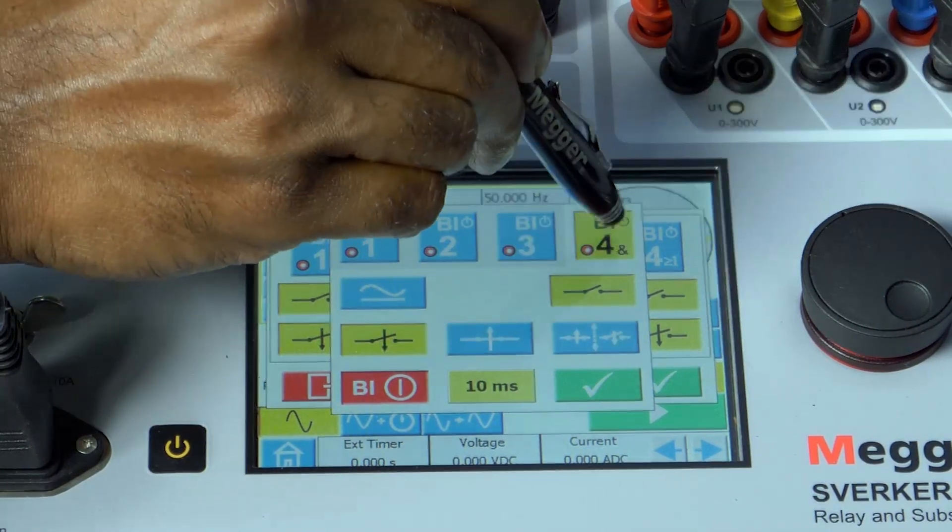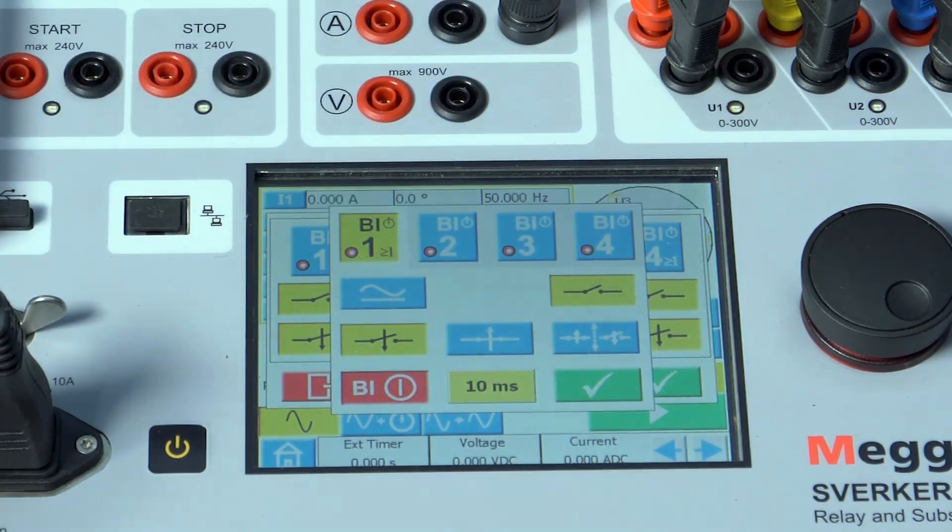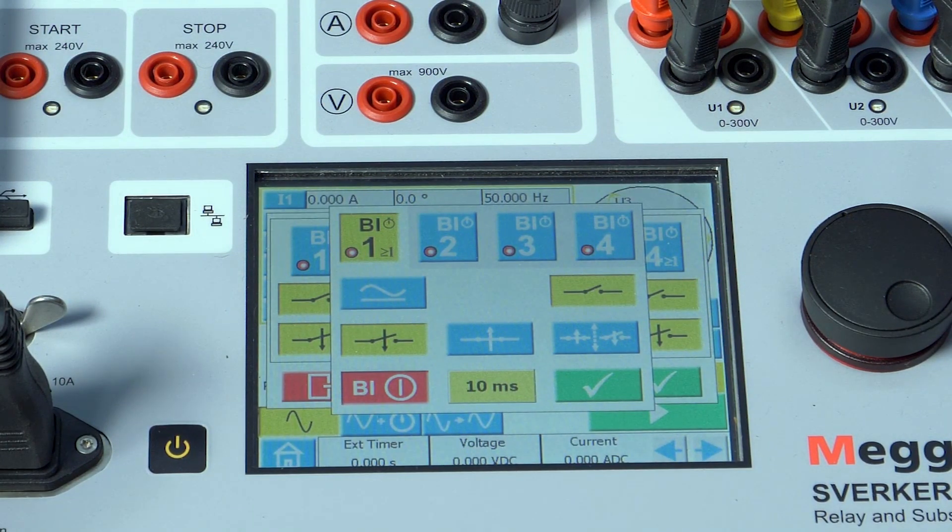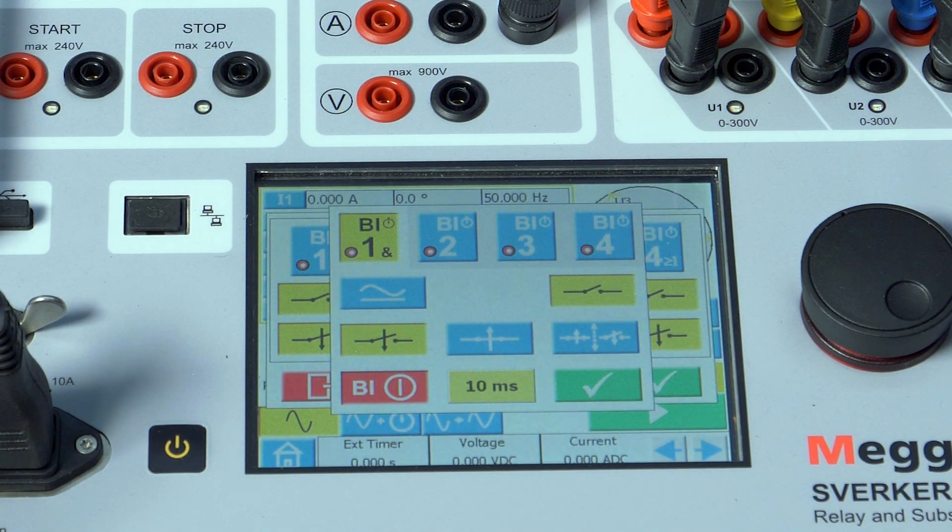The greater than or equal to 1 option means when the binary input which is chosen for this option becomes high, the kit stops the injection. Ampersand acts as an AND logic. That is, when ampersand is used for binary input 1 and binary input 2, then the kit will stop the injection only when both the binary inputs are high.